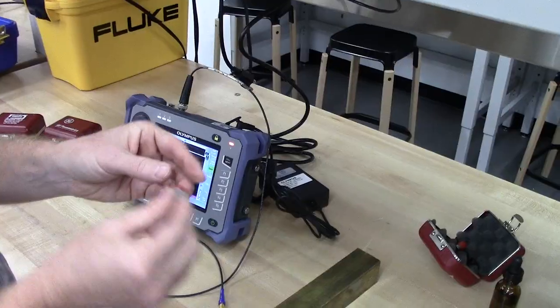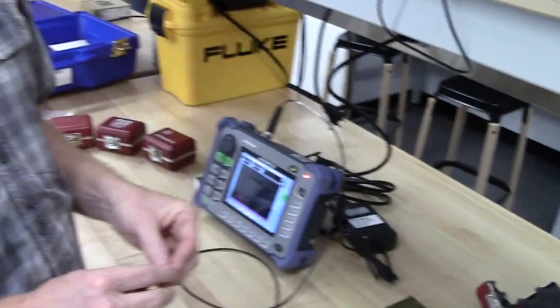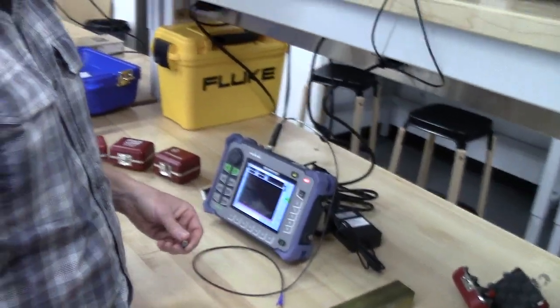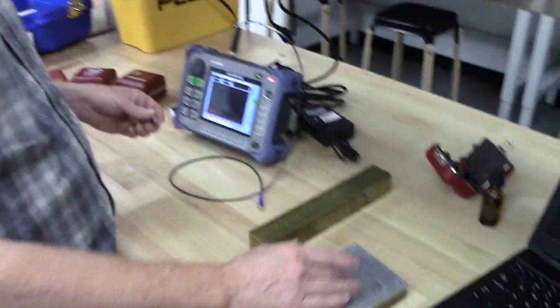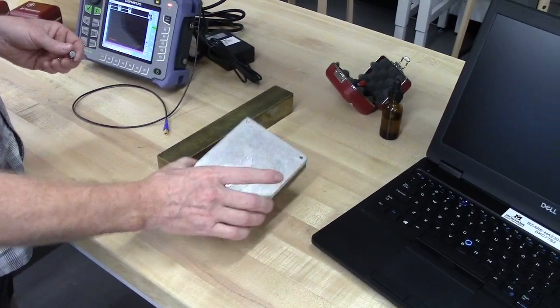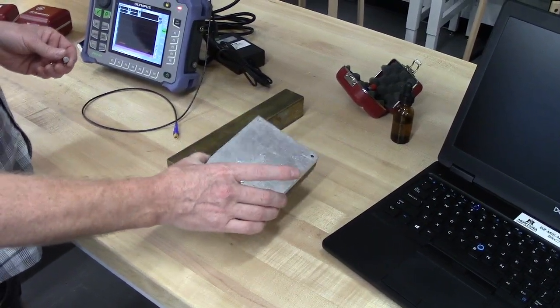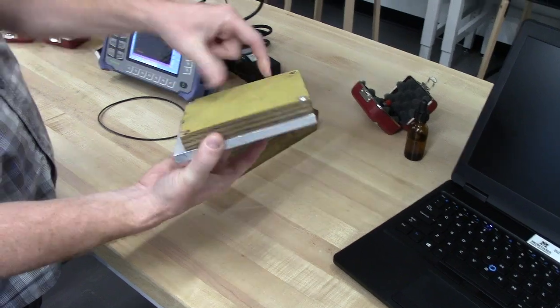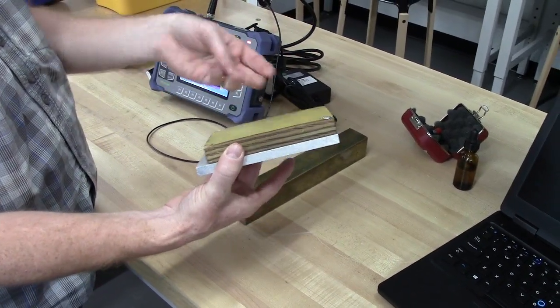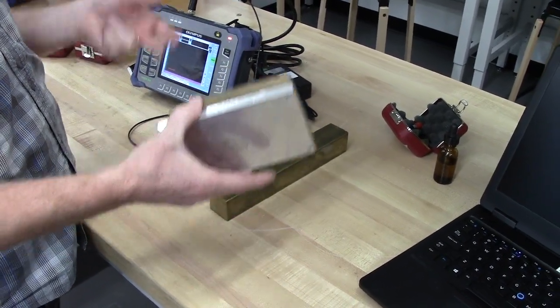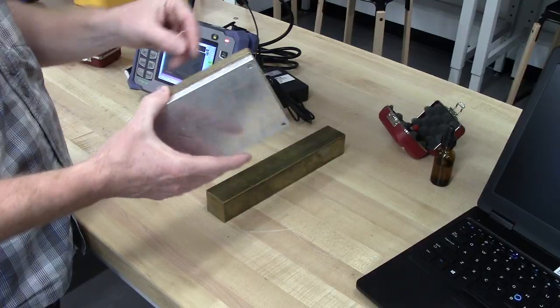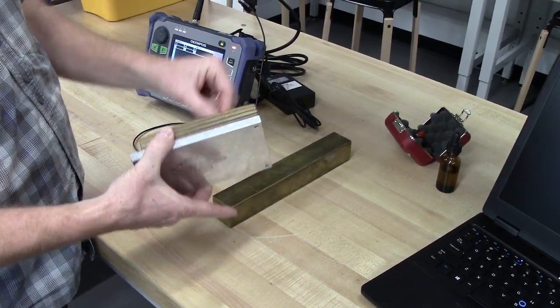So these transducers, when you get one from the box, it's probably going to come out like this. And there are a couple reasons why we want to use this one for the first part. And one reason is it's smaller. Because you are going to be using this to find the shape that has been machined out on the backside of this aluminum block. When you get it, it has this wood block covering it. But once you have finished figuring out what the shape is using ultrasound, then you'll open this up and see if you were right.